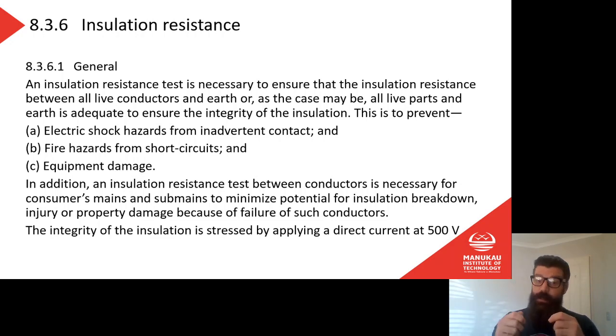So if you take the insulation resistance tester and you grab the two probes, you push the test button, it's going to give you a 500 volt electric shock. As I said, there'll be very little current there, so it's not going to harm you, but it will hurt. It's like getting a bad static shock off a trampoline or a car or something like that. And then the next question that you're going to ask, if you're anything like me, is can I try that? And my answer is no, you cannot try that. I do not give anybody permission to shock themselves or anybody else with 500 volts from the insulation resistance tester.